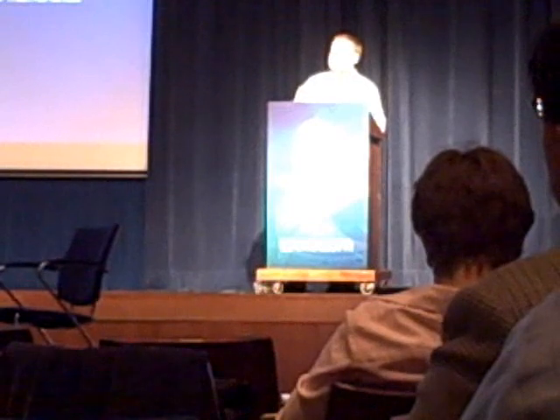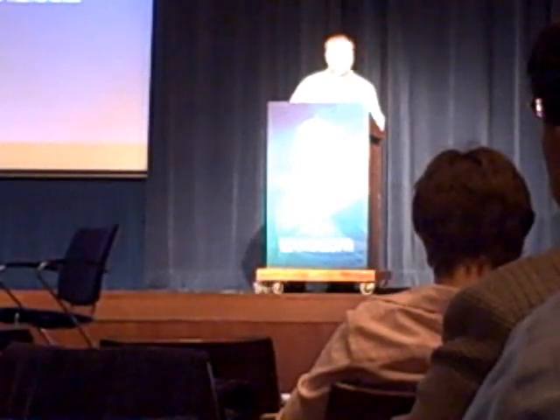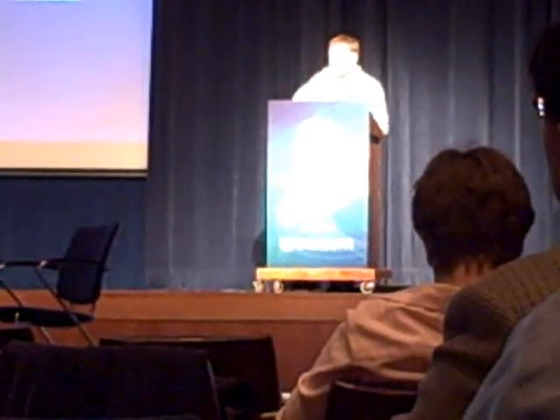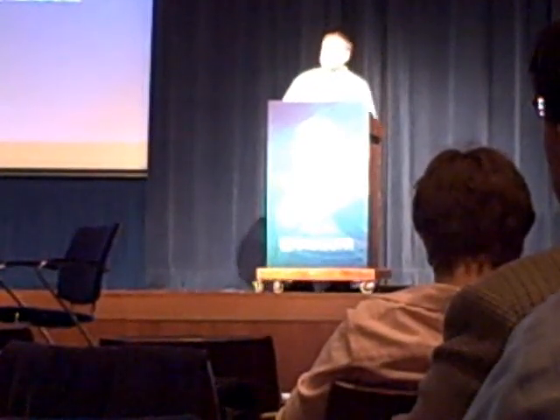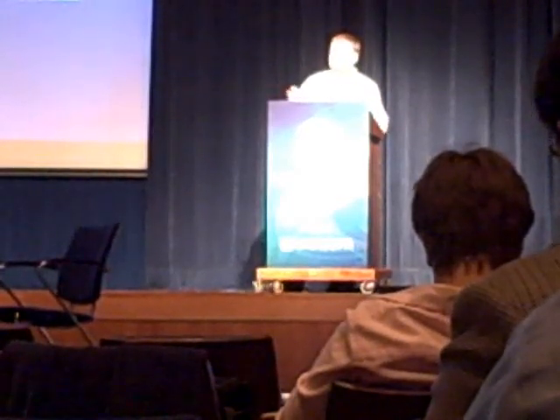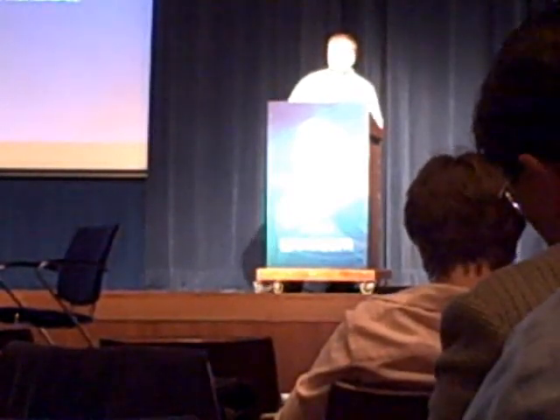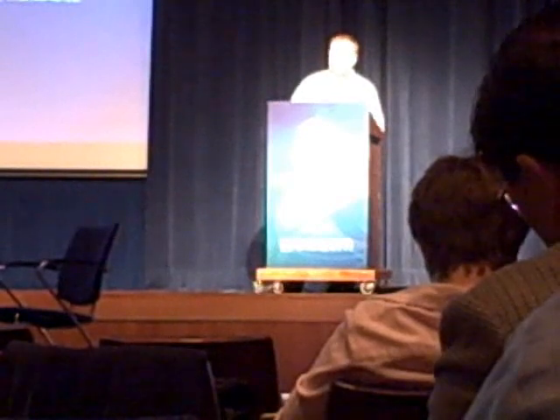These units are seen as unoccupied spaces, so there's no makeup air inside for people to be in there — we're only permitting processes on them. Regarding scale, our Chicago data center is going to install 100 to 200 container units on the ground floor with traditional colo space above, and each unit is anywhere from 300 to 600 kilowatts per container.